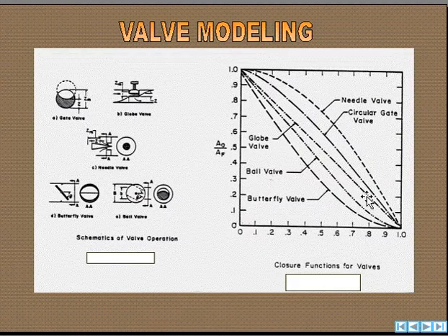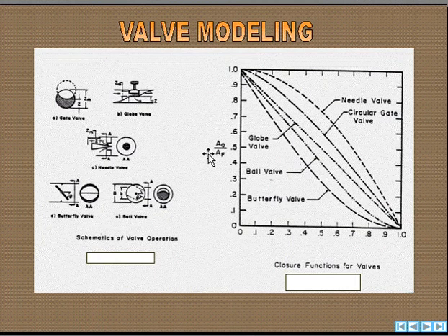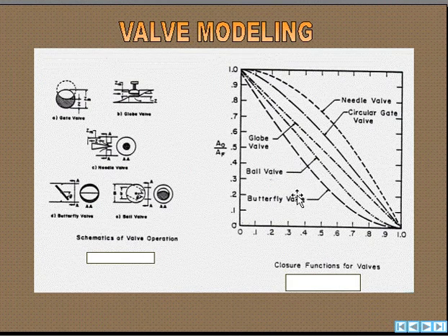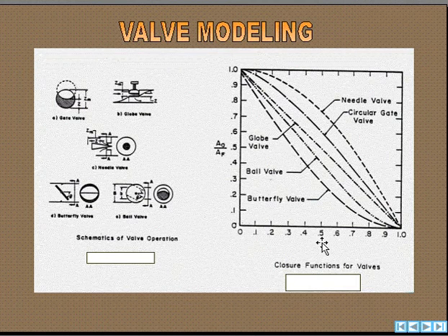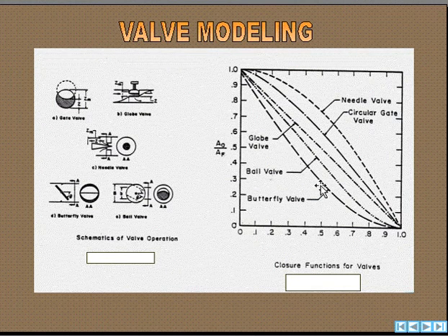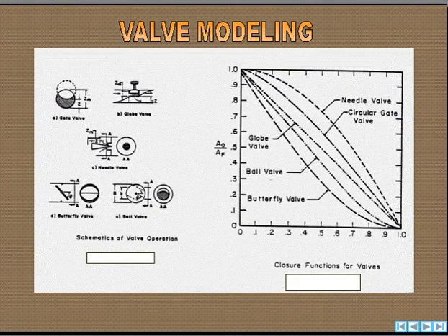The effective area through the valve versus the stem position is defined for various valves, and this technology is incorporated in Surge 2000. So if we say the stem has moved 50%, we can look up these built-in curves or functions and see what the effective open area of the valve is — that's calculated within the program.